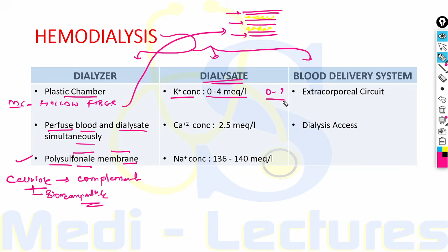Now the second component is dialysate, which is the fluid used during dialysis. The potassium concentration of dialysate is kept at 0 to 4 milliequivalent per liter depending upon the pre-dialysis serum potassium concentration. Usually it is not kept at 0 to 1 because of the increased risk of death due to arrhythmia, which occurs due to sudden potassium shifts. If we keep the potassium concentration very low, there can be a risk of arrhythmia due to sudden potassium shifts. So it is kept in a range of 2 to 4.